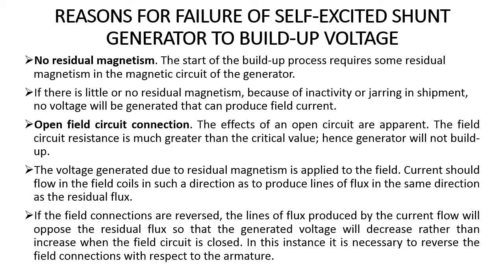If there is little or no residual magnetism because of inactivity or jarring in shipment, no voltage will be generated that can produce field current. The second one is an open field circuit connection. If the field circuit is open circuited, then that resistance is a very high value, more than the critical value. The field resistance is more than the critical field resistance, hence the generator will not build up.